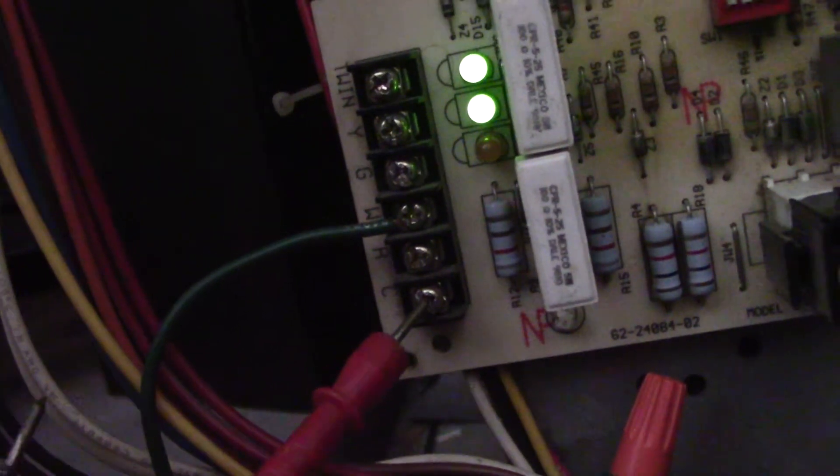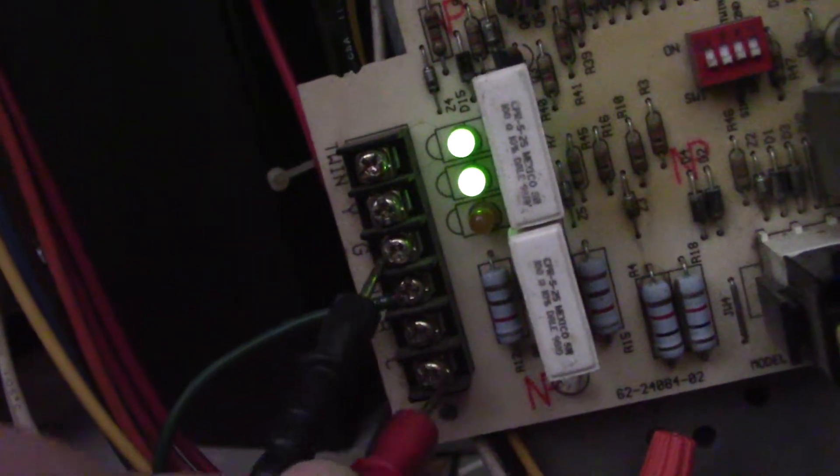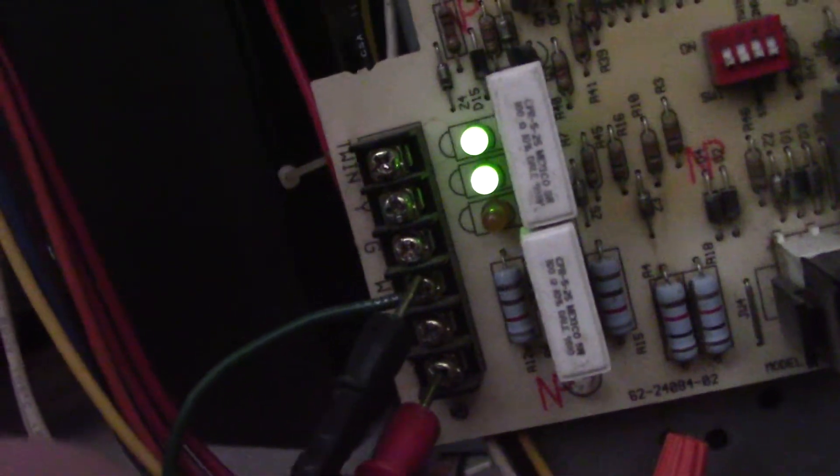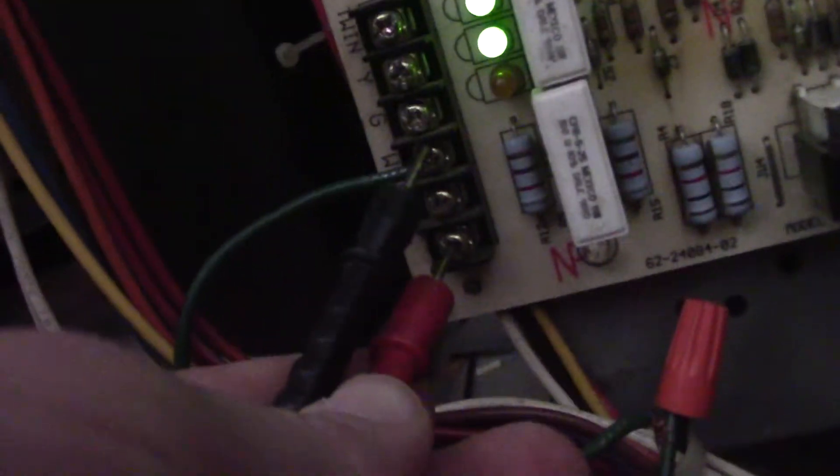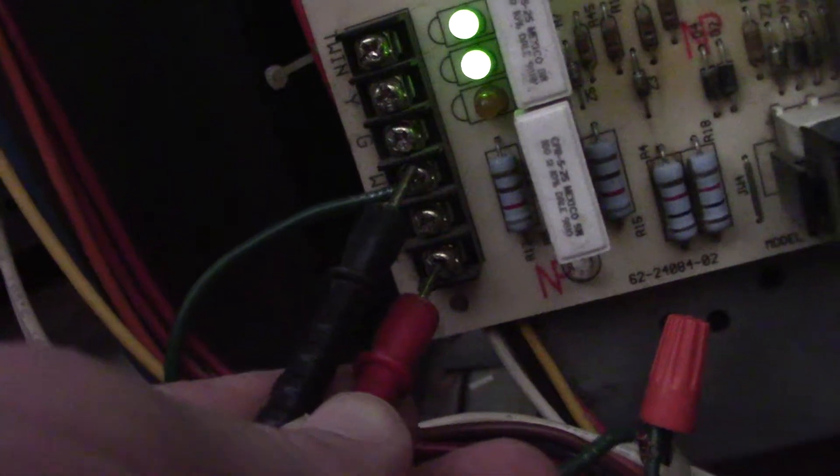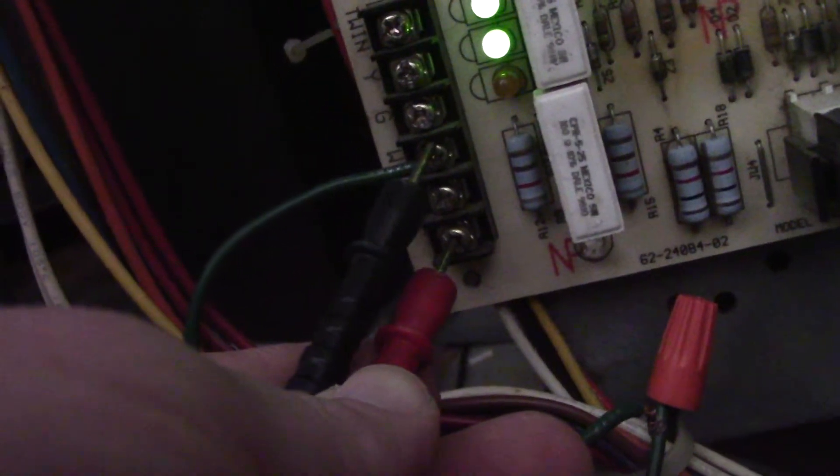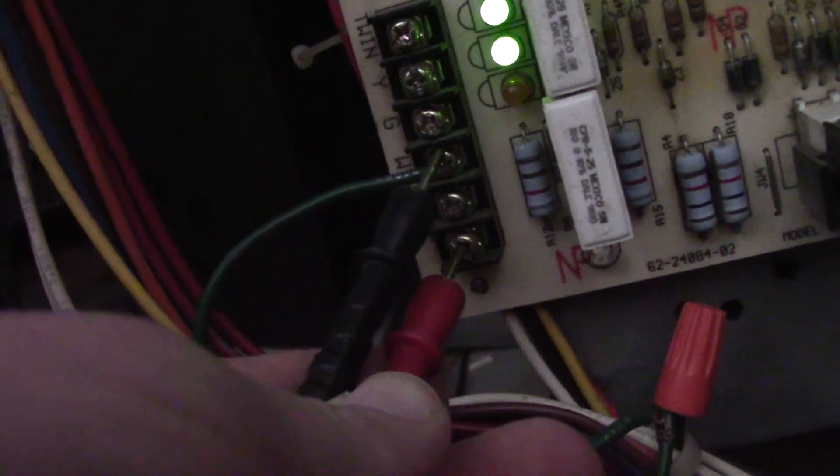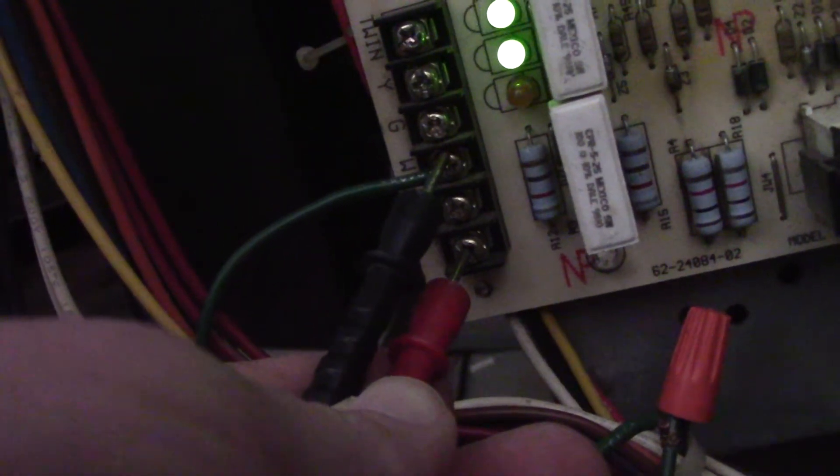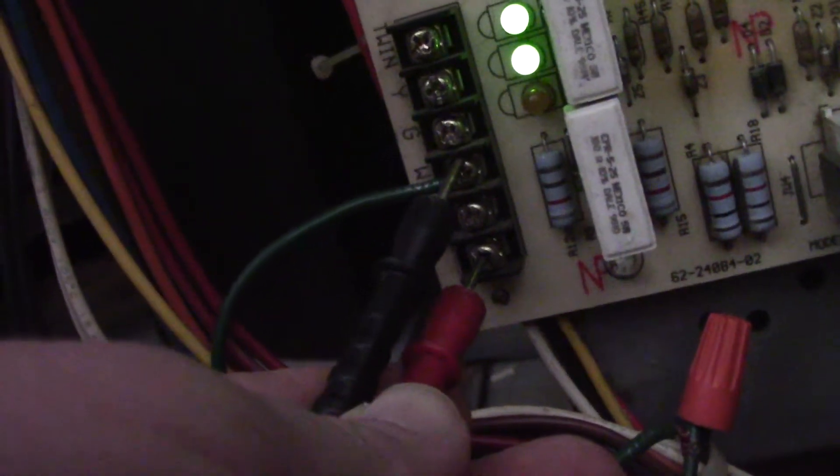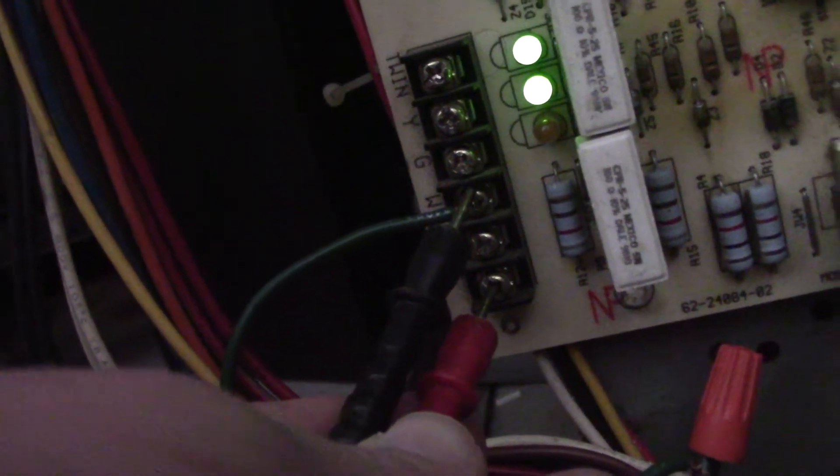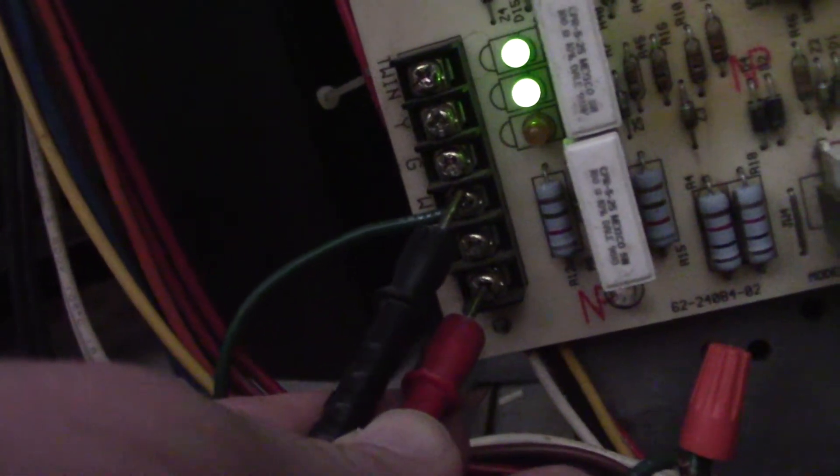If you go W to C with a call for heat from the thermostat, you should have a 24 volt reading. If you have a zero volt reading, you've got a problem at your control wires or at the thermostat.